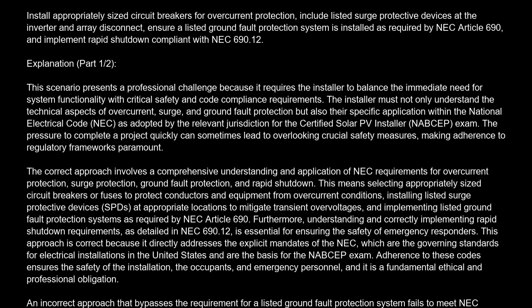frameworks paramount. The correct approach involves a comprehensive understanding and application of NEC requirements for overcurrent protection, surge protection, ground fault protection, and rapid shutdown. This means selecting appropriately sized circuit breakers or fuses to protect conductors and equipment from overcurrent conditions, installing listed surge protective devices, SPD, at appropriate locations to mitigate transient overvoltages, and implementing listed ground fault protection systems as required by NEC Article 690. Furthermore, understanding and correctly implementing rapid shutdown requirements, as detailed in NEC 690.12, is essential for ensuring the safety of emergency responders.